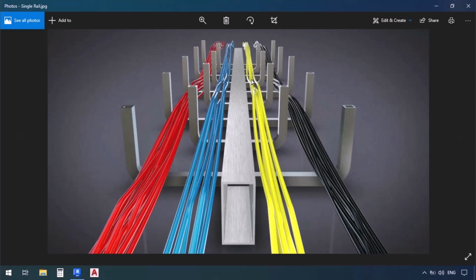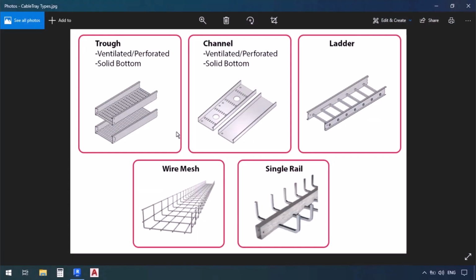As you can see here in this image, these cables which are going through, there is some distance between each hook, and it seems like the cables are weighing down between them. So they are going forward kind of wavy, but there are actually some cables which are not supposed to go that way or be weighing down. For example, the optical fiber cables. They're not supposed to have so many curves.